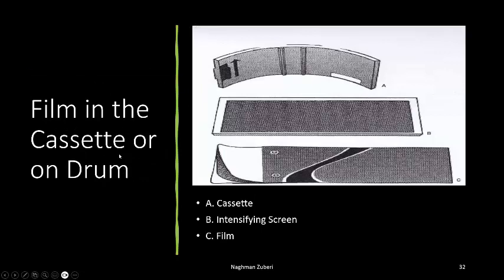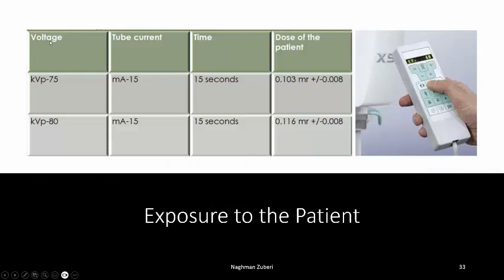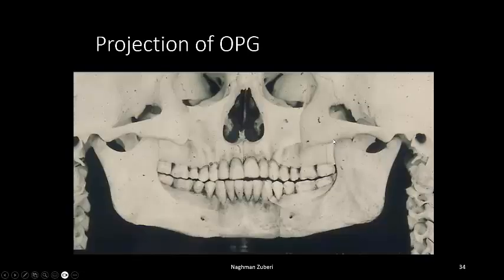The film is housed in a cassette with an intensifying screen. Using proper kilovoltage, current, and time, the dose to the patient can be calculated: at 75 kVp and 15 mA for 15 seconds, it will be 0.103 mR ± 0.008; at 80 kVp and 15 mA for 15 seconds, it will be 0.116 mR ± 0.008. This is how three-dimensional structures of the human face appear on a flat screen in an OPG.